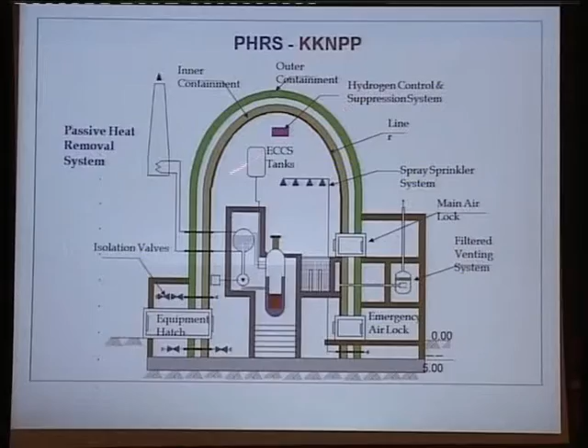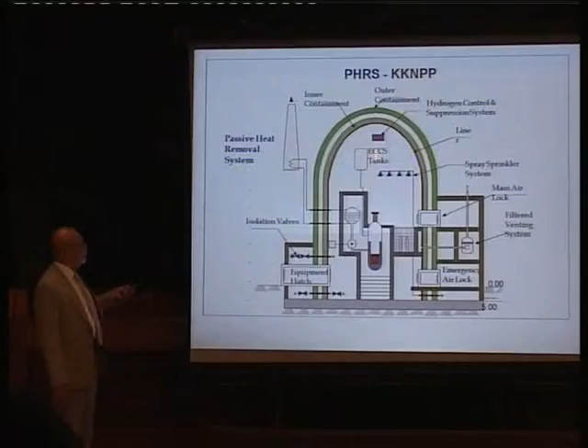Now, emergency core cooling is provided by special tanks. Then there are what we call spray systems, which can bring down the pressure inside if there is any steam formation. Then we have a hydrogen control system, with many hydrogen catalytic recombiners in case hydrogen builds up, so it doesn't go through a combustion process. The hydrogen is recombined and made into water, so there's no risk of explosion.